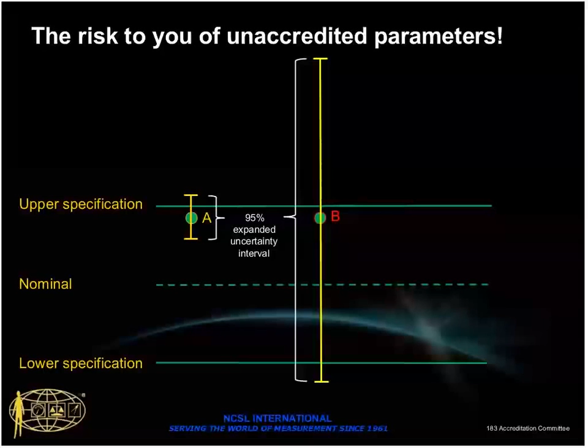As we mentioned earlier on, and as Trevor was, the ISO GUM, or the so-called GUM, the Guide for Expression of Uncertainty of Measurement, I'm showing two yellow intervals here, and these would represent the statistical interval over which you'd have a 95% expanded uncertainty interval. And so what that really means is that when we look at these two measurements, it's two different laboratories, but I'm going to show you that the areas that are shown in red, the true answer, we don't really know where the true answer is.